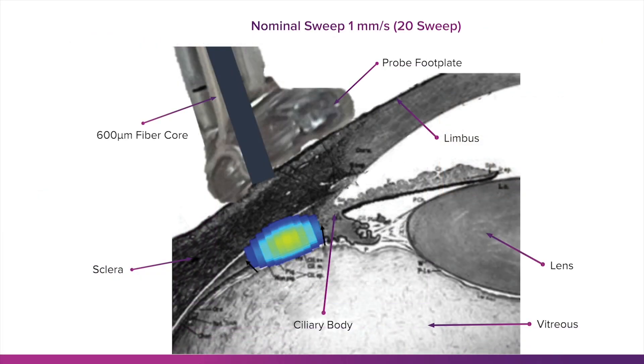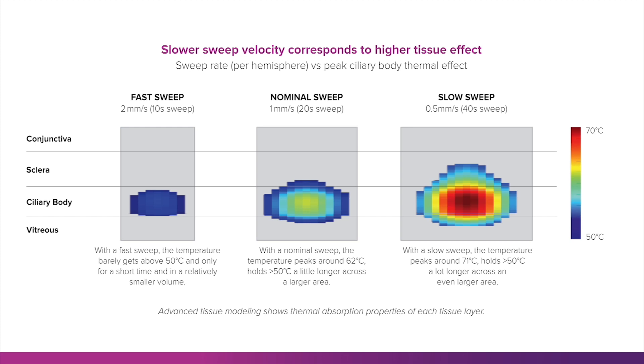Here, the tissue temperature increase is illustrated in relation to the placement of the Micropulse P3 Probe. As shown in this image of advanced tissue modeling, a fast sweep of the Micropulse P3 Probe causes minimal temperature rise. As the sweep speed is slowed, tissue temperature increases. The goal is to safely achieve the desired clinical effect without under- or over-treatment.